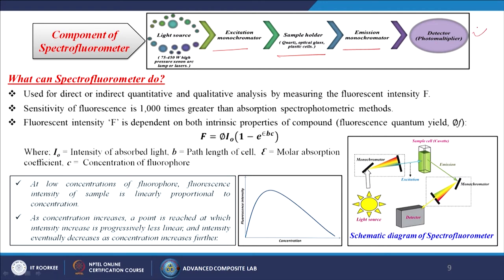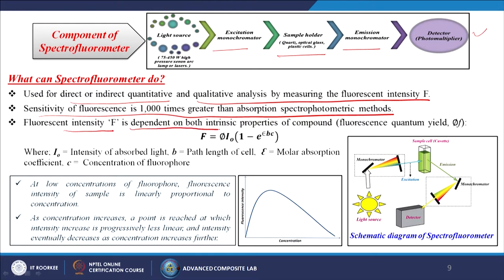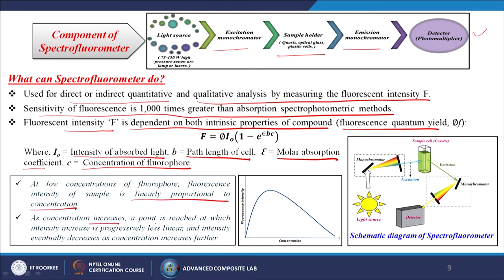A spectrofluorometer is used for direct or indirect quantitative and qualitative analysis by measuring the fluorescent intensity F. Sensitivity of fluorescence is 1000 times greater than absorption spectrophotometric methods. Fluorescent intensity F depends on both intrinsic properties of the compound — fluorescence quantum yield φF — and: F = φ·I₀·(1 - e^(-ε·B·C)), where I₀ is the intensity of absorbed light, B is the path length of cell, ε is the molar absorption coefficient, and C is the concentration of fluorophore. At low concentration fluorescence intensity is linearly proportional to concentration. As concentration increases, the intensity increase becomes progressively less linear and eventually decreases.